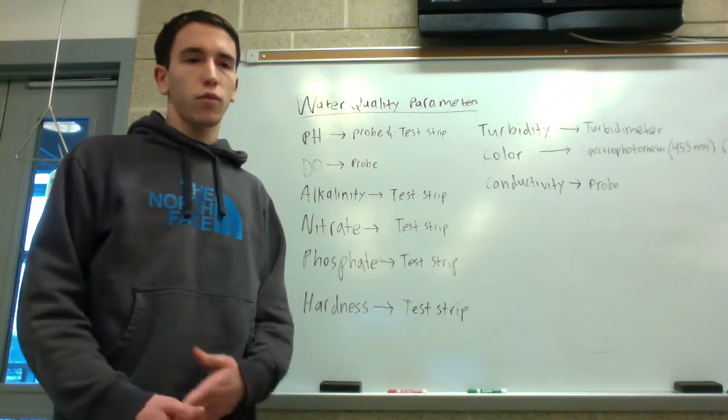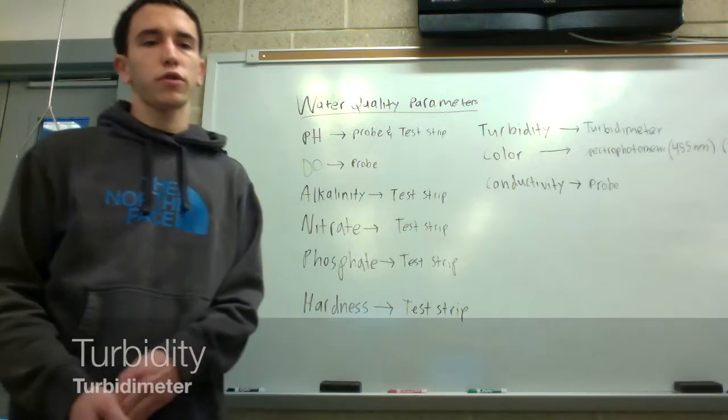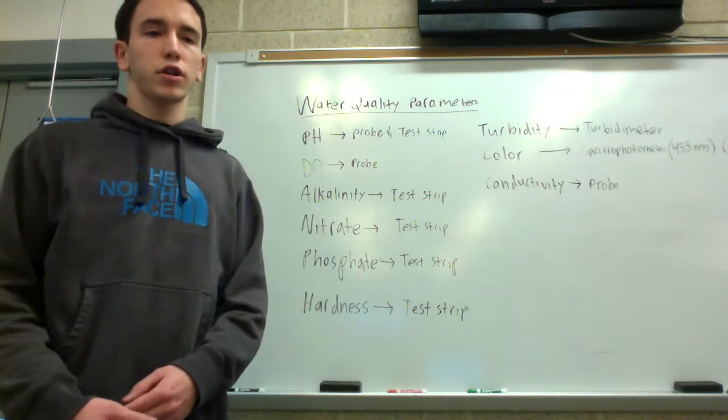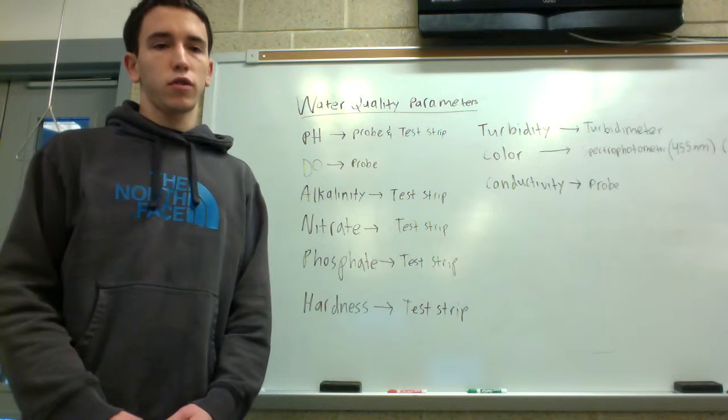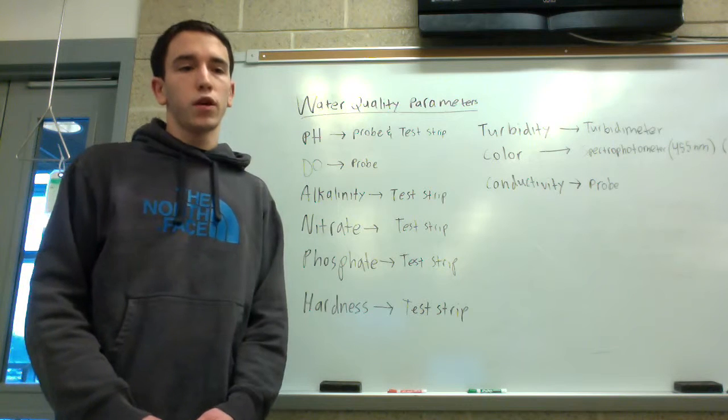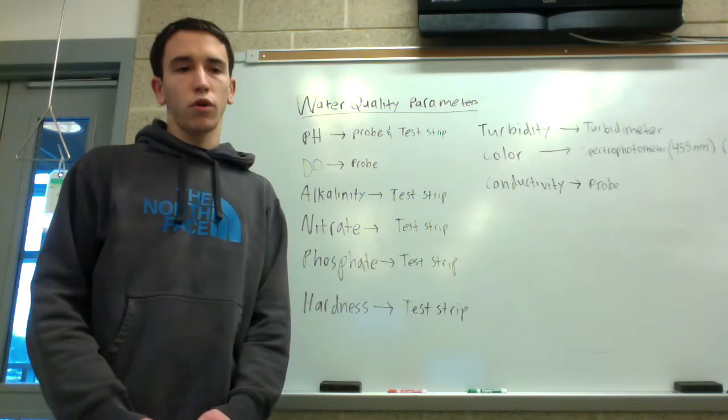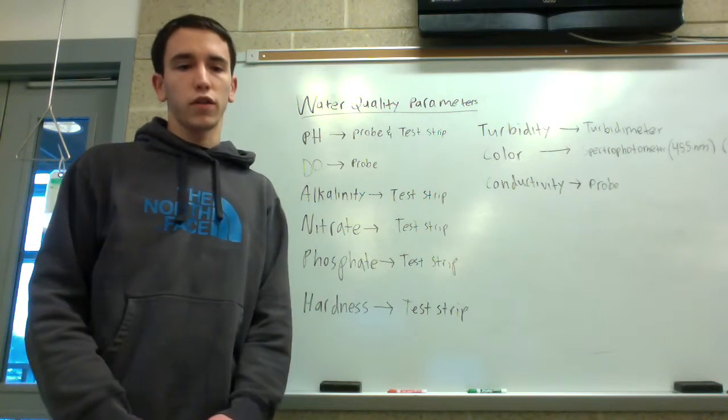Next you'll determine the turbidity of your sample, which is the tendency of water to scatter light. It's measured in NTUs and determines the amount of suspended solids present in your water sample. Less than 5 NTUs appears clear. Disinfected water should be below 1 NTU.